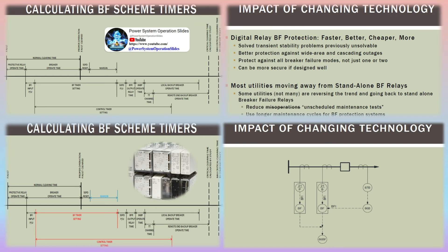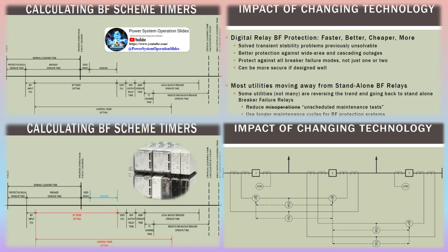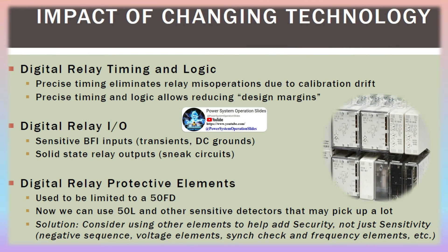Breaker failure protections are used on breakers at any voltage level, but are predominant on 138 kV systems and above. The more impact a failed breaker will have on electrical system stability, the more necessary it is to use high-speed breaker failure protection. Lower voltage levels of 13.8 kV and below may use timed backup protections if the fault clearing time is not crucial.